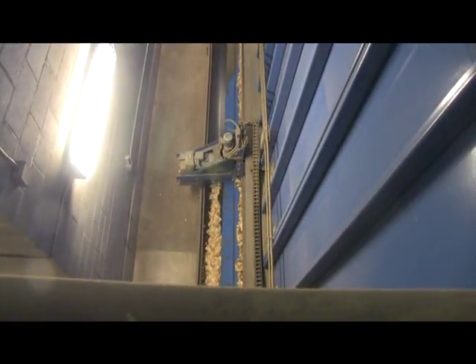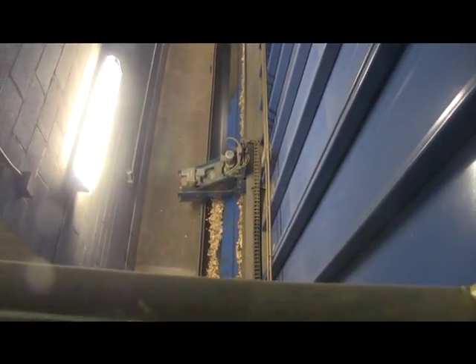We do periodic maintenance on a monthly basis, on a daily basis, and on a yearly basis. We actually just got through our boiler inspections last week. So the boilers were down for about 5 days. It takes 3 days to cool the boiler off to a temperature where you can actually get into the boiler and clean it. And then we have a boiler inspector come and inspect the internals of the boiler to make sure it's operating properly. So that's a yearly thing that we do.